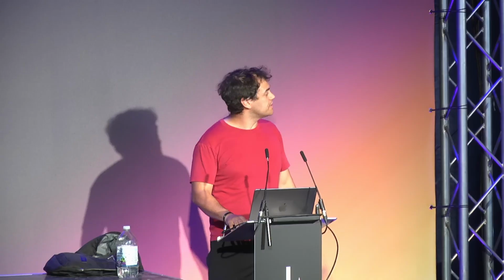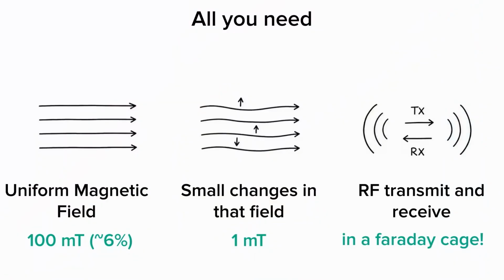So if you don't need these 3 things, what 3 things do you need? One is a uniform magnetic field. So the scanner we built was about 100 millitesla, which is approximately 6% of the field strength of those ones that you get in a hospital. And then you need something which makes small changes in that field. So the one we built, you've got 100 millitesla main field, and then you change that field by about 1 millitesla from one part to the other.